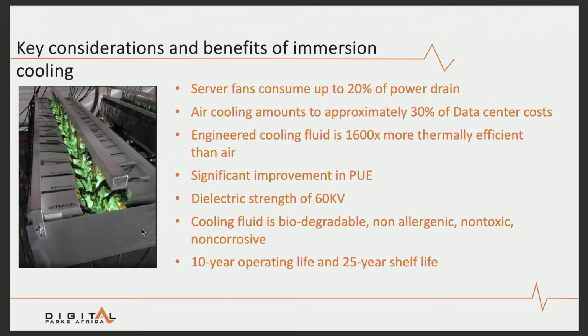These liquids have a high dielectric strength, so they are very much non-conductive, up to 60 kilovolts, higher than traditional mineral oils. I think for those of us who are electrical engineers and used to using mineral oils in transformer cooling and other applications, these special fluids are engineered for server cooling. They have better dielectric characteristics. Biodegradable is very important, obviously. They have a long operating life of 10 years in the tank and 25 years shelf life, and they're completely safe for human ingestion, even human touch.